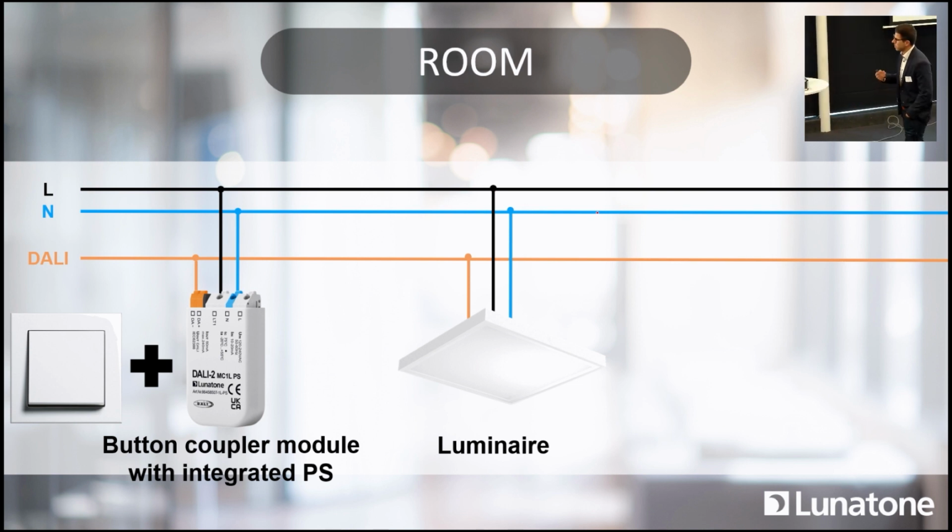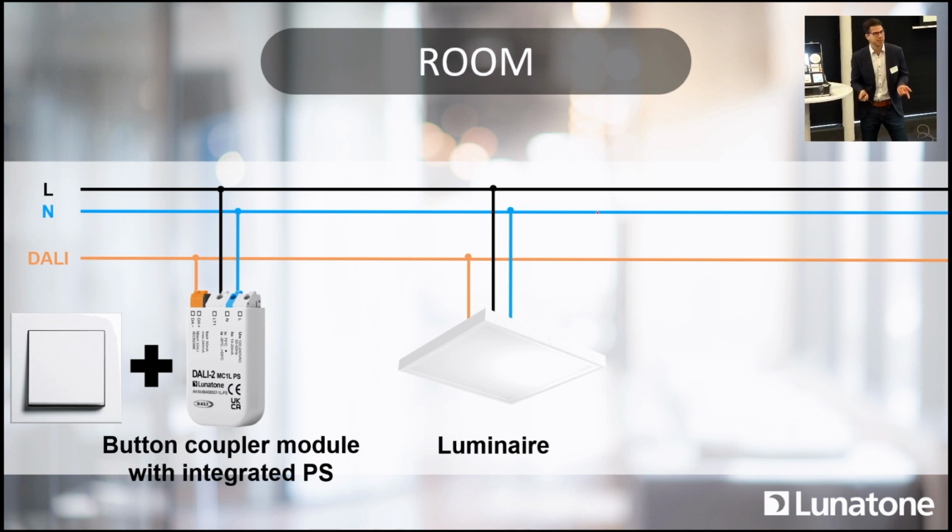Of course, if you want to set up devices to a different behavior, then you need to access those devices and do the configuration. But if you have an installation and, for a few weeks, maybe somebody who does the configuration is not ready, you can set up these devices already, and they control the light in a simple way. And this comes with a DALI bus power supply, and that's why you don't need a separate device for the bus power. So it's a very simple and neat setup.